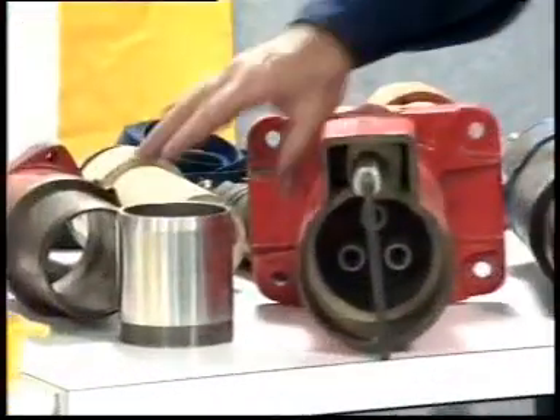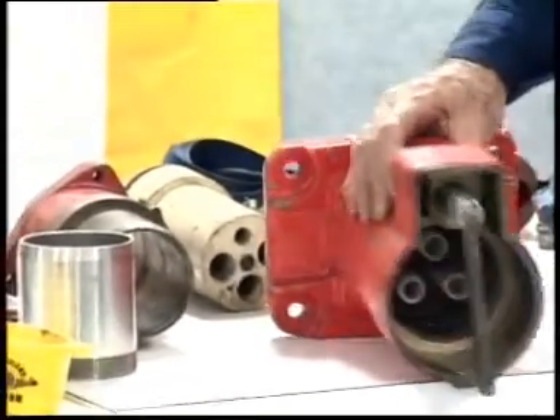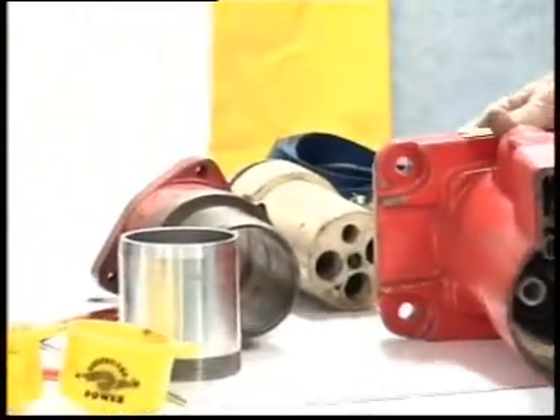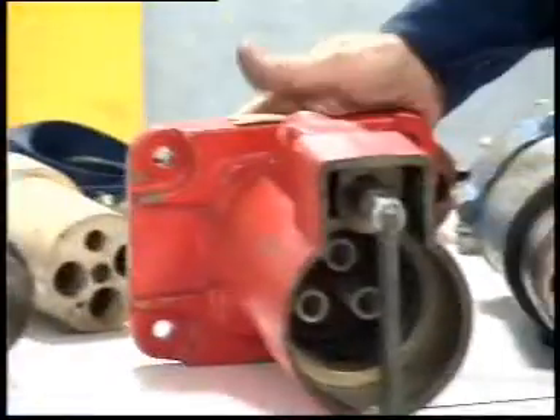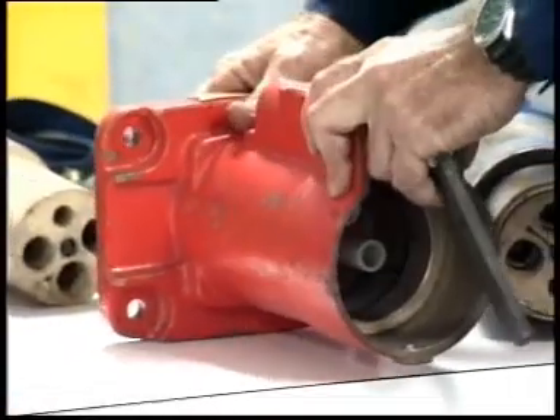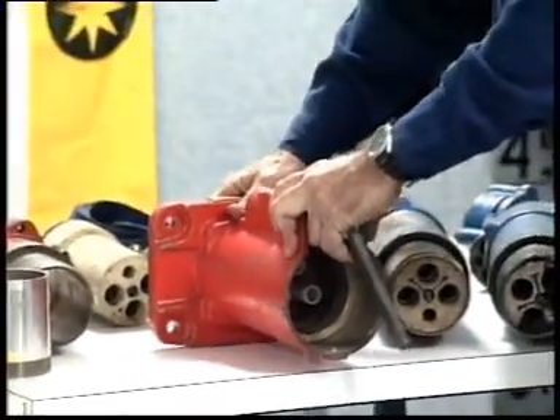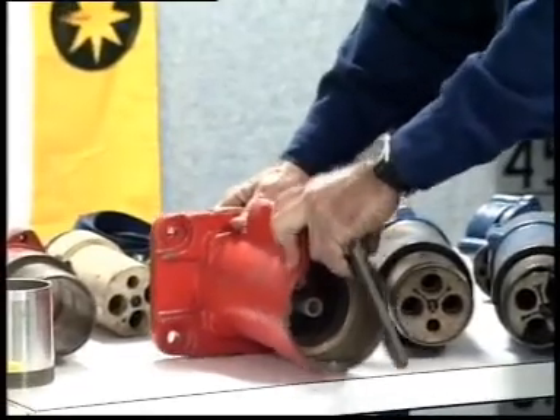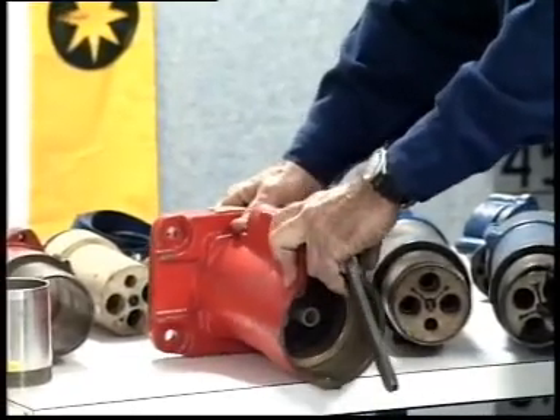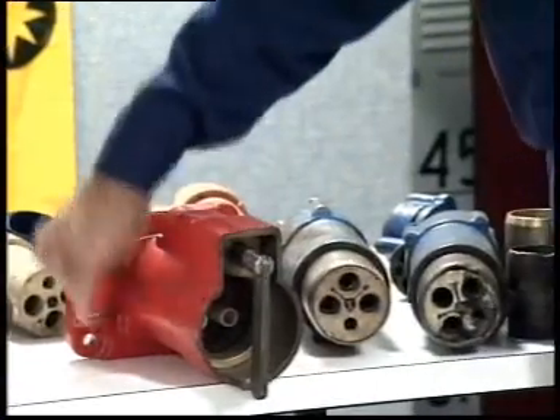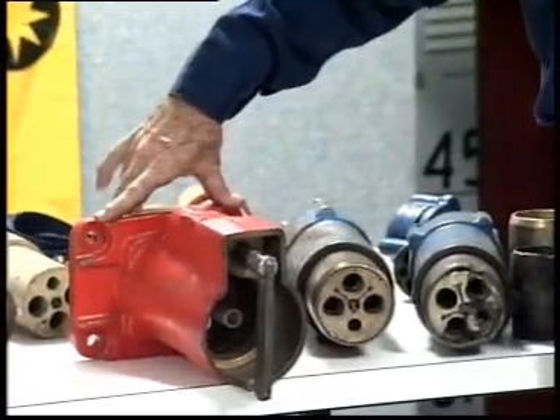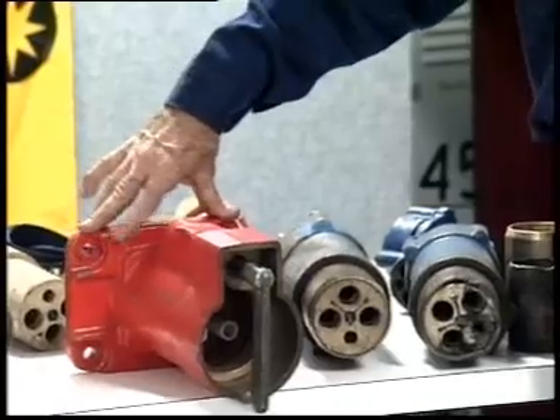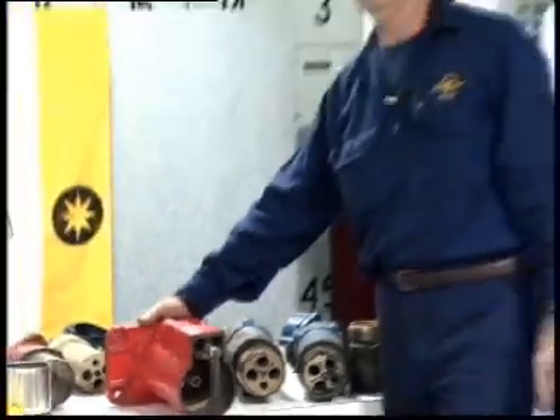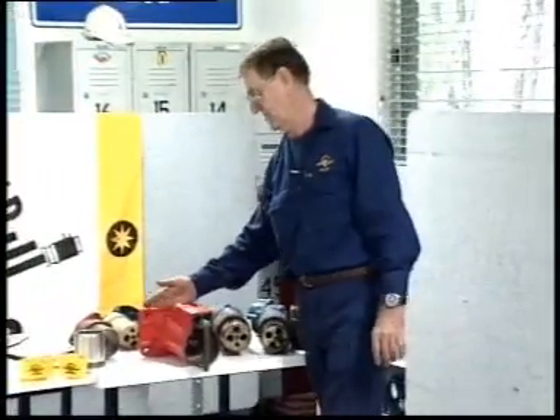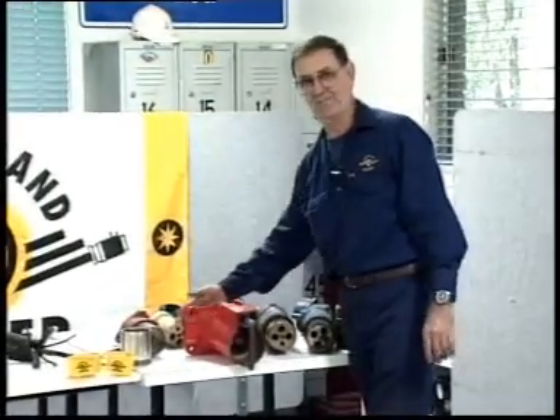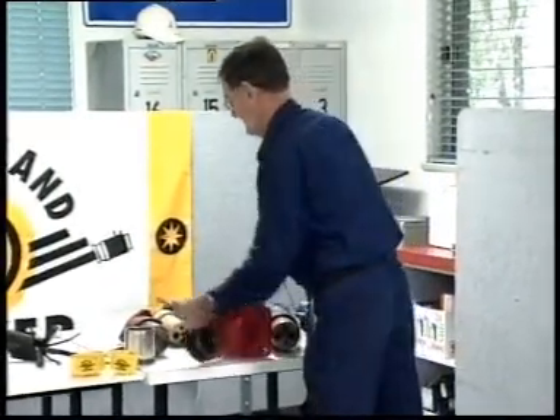When you come up to these receptacles, and you've all seen them, back to back is just two of these together, on a frame. When you come up to them, first thing to do is to just try that receptacle and make sure that it's not wobbly at all. I mean, it won't be wobbly like that, but just make sure it's not loose. If it is, there's a chance that the bolts holding it could be loose. And if they are, you do not tighten them up. You get your section electrician to do it, because he has to come and ensure that the flame path gap on the back of this thing is correct.